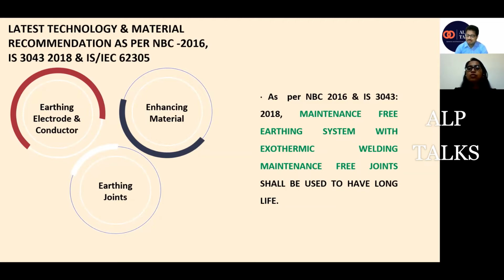Right. So now the latest standards are recommending maintenance-free earthing. What is maintenance-free earthing? That is the chemical which we use to lower the resistivity. It helps us in making the system maintenance-free also, because these are carbon-based compounds. Carbon has a property that it locks in moisture. So once we install it, it will remain as it is for as long as the earthing is there, and it will lock its moisture. It does not need watering of the pit on a regular basis. It does not require any maintenance. And it will not need to extract moisture from the surrounding soil, as there are bentonite-based compounds also in the market. Bentonite has a disadvantage that it extracts moisture from its surrounding soil.